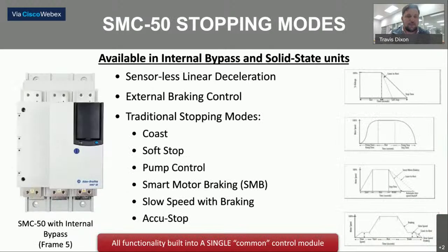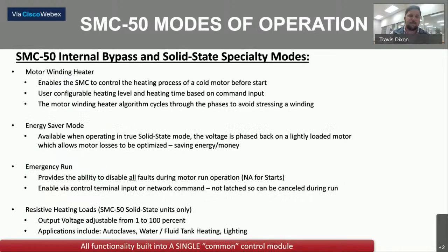Transitioning into SMC 50 stopping modes. This is for both the internal bypass and solid state units: the sensorless deceleration, external braking control, and all the traditional stopping modes. The sensorless linear deceleration is also a patented mode specific to the SMC 50. So this is some of the additional modes of operation you get with the SMC 50. The motor winding heater is used to heat the motor winding so that condensation develops on the outside of the motor and not the inside.